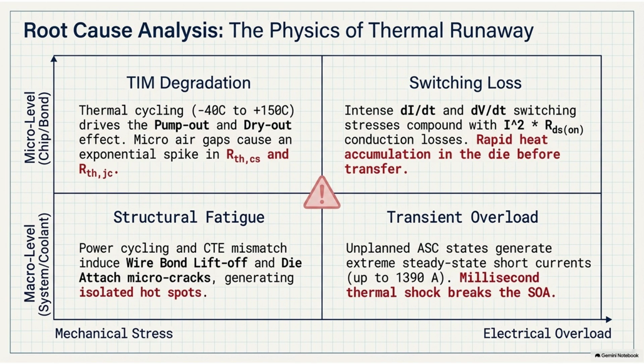We just discussed the CTE mismatch warping the heavy base plates, but that same differential expansion is happening on the microscopic scale on top of the chip. You have ultra-thin aluminum or copper wire bonds connecting the top of the silicon die to the circuit board, and these wires are carrying hundreds of amps. As you push huge amounts of power through the system over thousands of driving cycles of active power cycling, the silicon die and the copper wire expand at different rates.